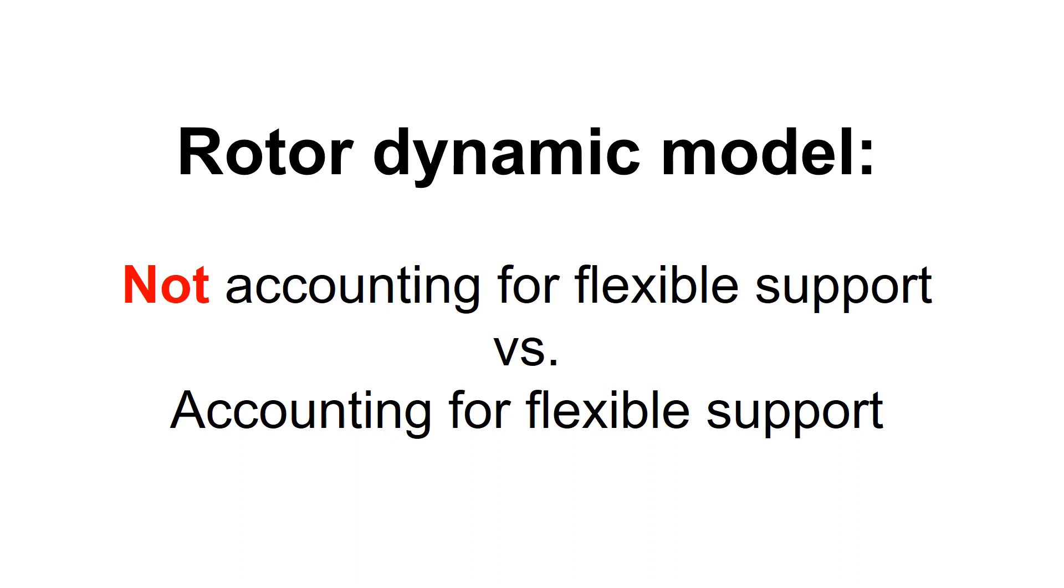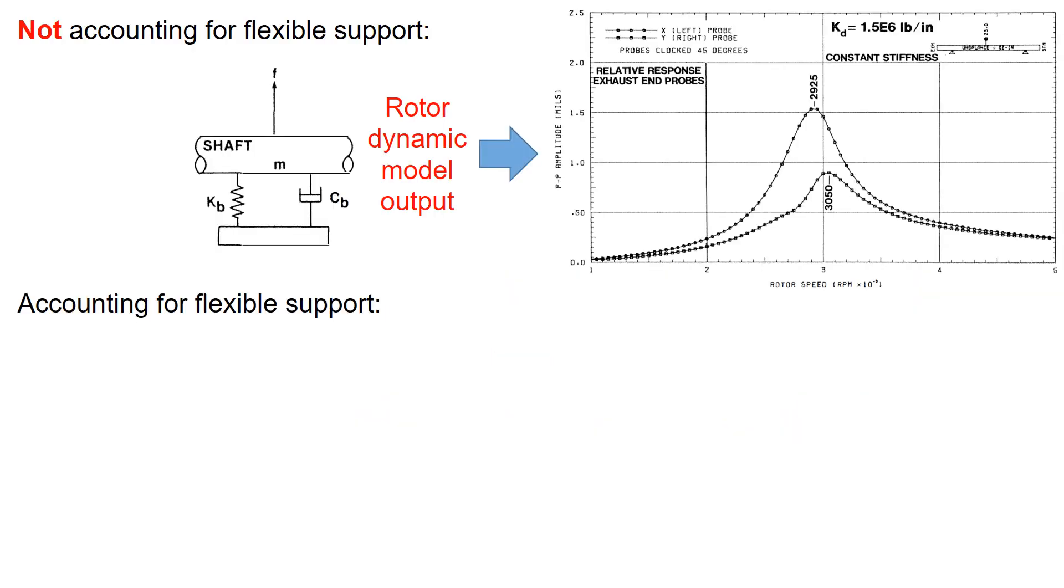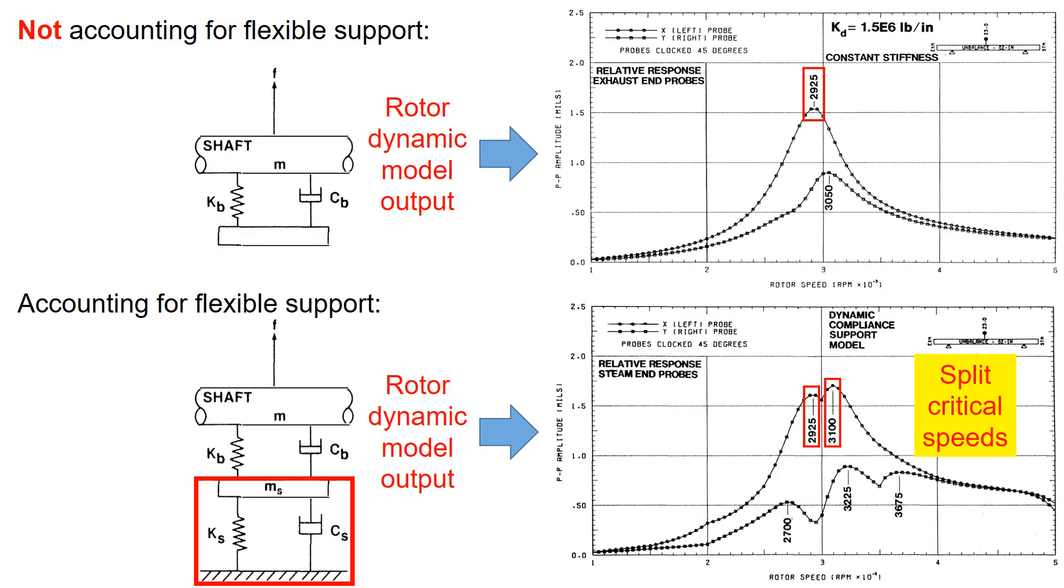Now let's compare two scenarios: accounting for flexible support in the model versus not accounting for it. When the rotor dynamic model accounts for flexible support, it predicts split critical speeds, while the one without only shows a single peak.